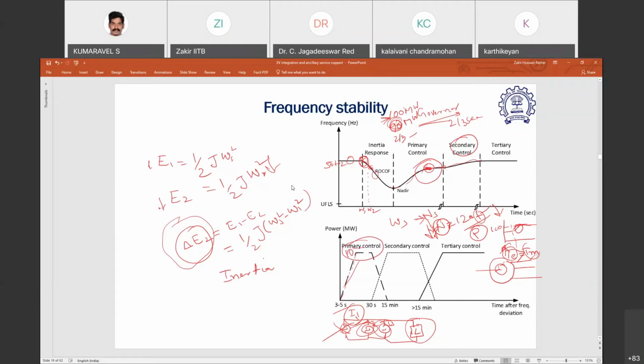So therefore, to make these generators which are participating in primary frequency control ready for the next possible event, we have to release them from the primary control. It means they should come back to their earlier generation, in this particular case 90 megawatt again, such that if there is a new event happening, it should again be ready to release this 10 megawatt to the grid. That is precisely what releasing the primary reserve means.